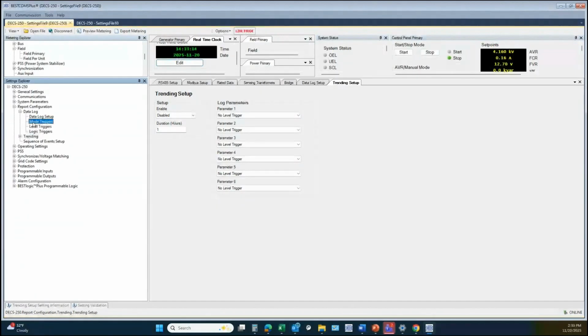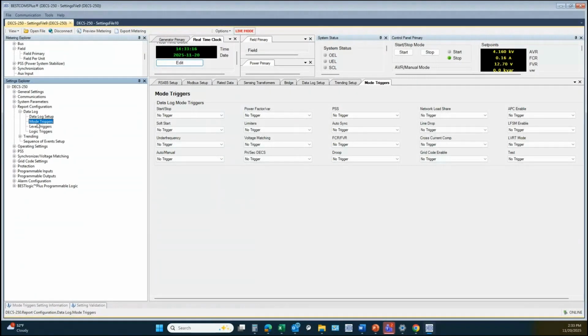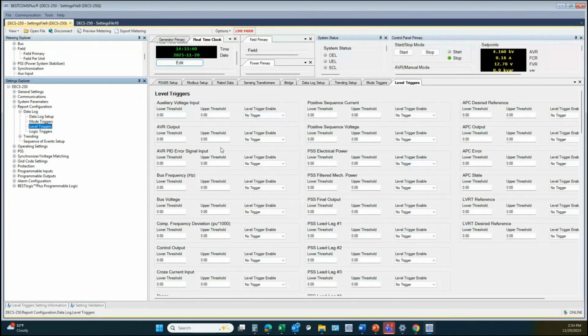I apologize, I skipped to trigger the data logs. There needs to be something selected. So you can trigger on a start. You can trigger on the OEL or UEL becoming active. There are numerous options for triggering on different modes or different levels. If your voltage got too high or too low, you could trigger a data log on those events. And there's also logic triggers.